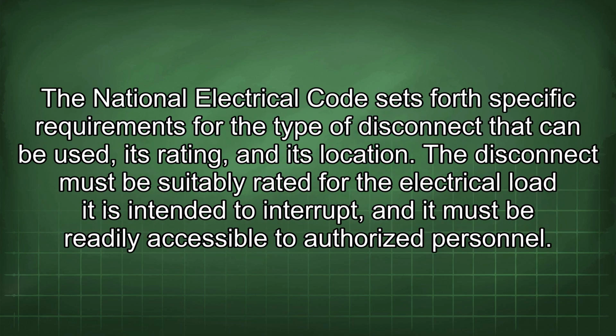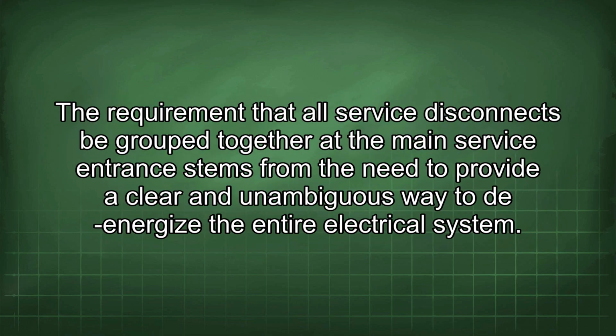The National Electrical Code sets forth specific requirements for the type of disconnect that can be used, its rating, and its location. The disconnect must be suitably rated for the electrical load it is intended to interrupt, and it must be readily accessible to authorized personnel. The requirement that all service disconnects be grouped together at the main service entrance stems from the need to provide a clear and unambiguous way to de-energize the entire electrical system.